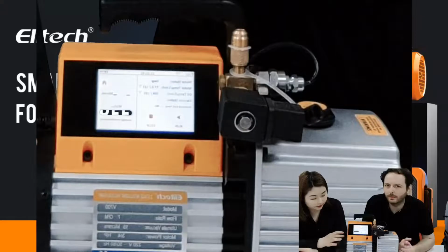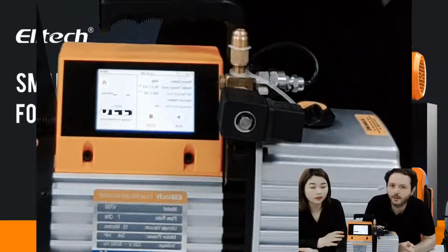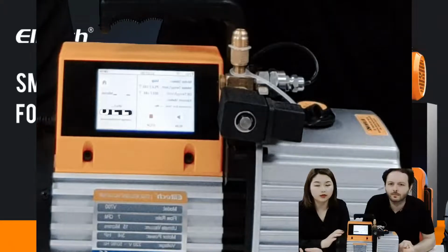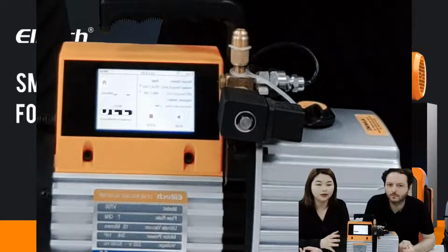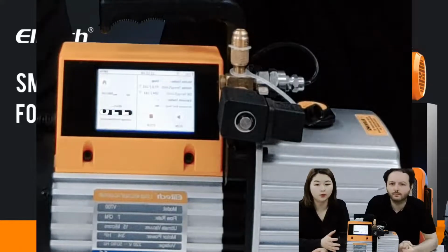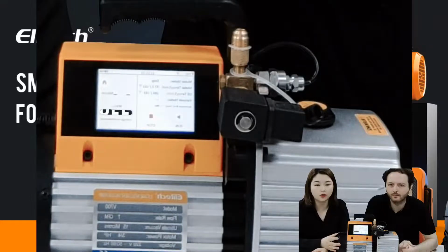Also, it has a good feature about estimated job completion time. It shows us how long the pump will take to reach the target value we set, helping us make better schedules. Since we know how long it will take, we can use the spare time to do other work and know when to come back to check on the pump. When the target vacuum is reached, a pop-up window appears on the screen to remind us.